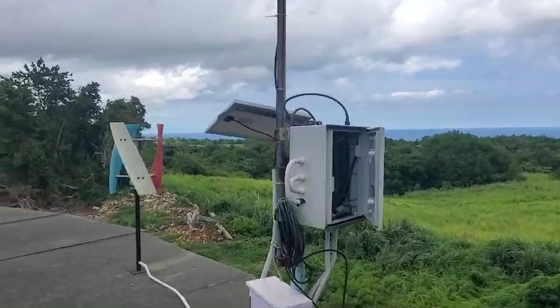This main server runs the Ignition SCADA and centralizes the communications with all remote stations with its powerful driver, providing a 20 seconds update time for the 32,000 remote variables managed, located on 65 PLC's memory.